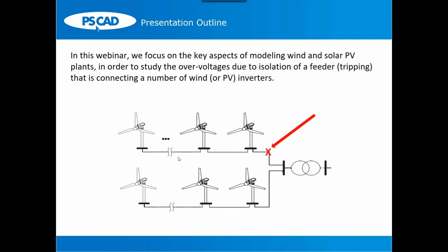There have been many reported instances of tens of surge arresters getting damaged due to this phenomenon on collector system feeders. Now, if this is an offshore wind farm, you don't want this to happen, because if the cables get damaged, that would have serious consequences. So this is a very specific study.